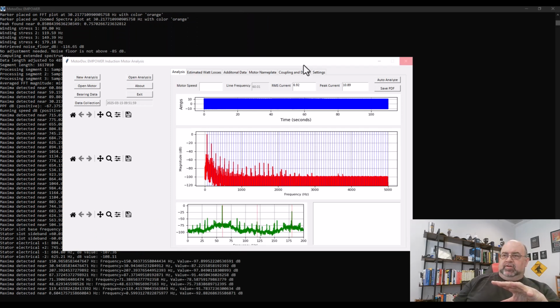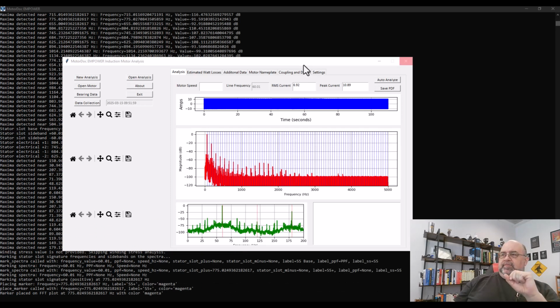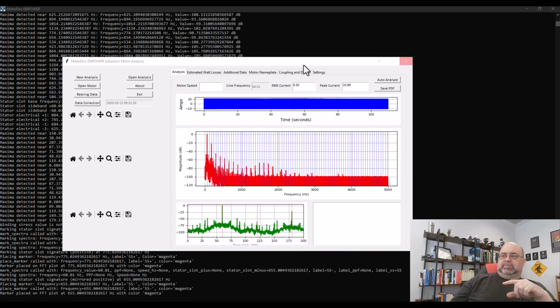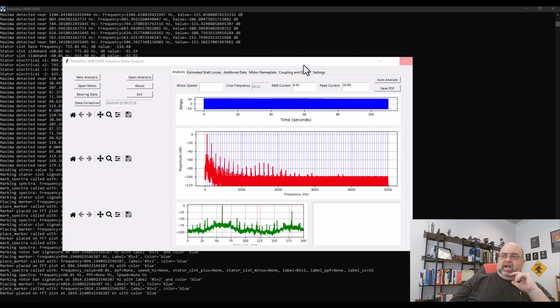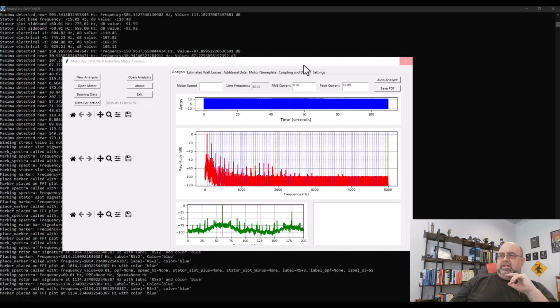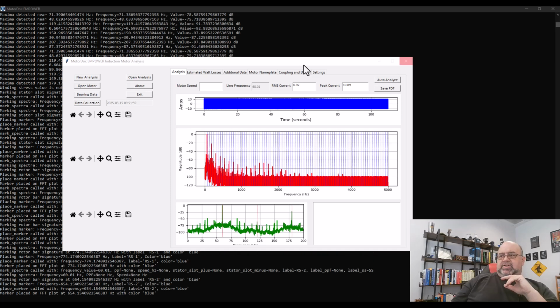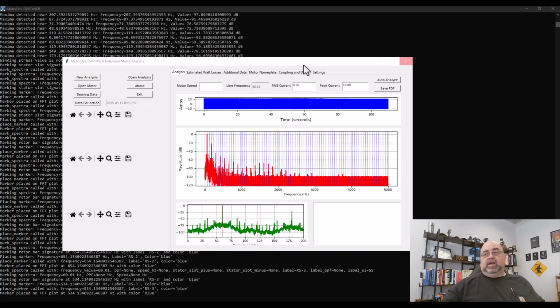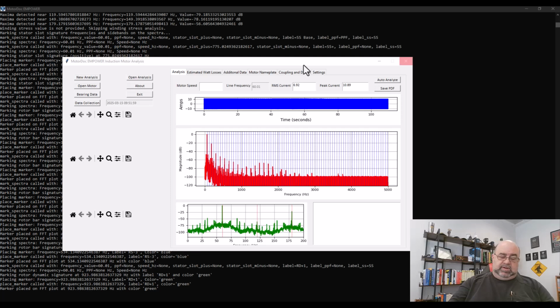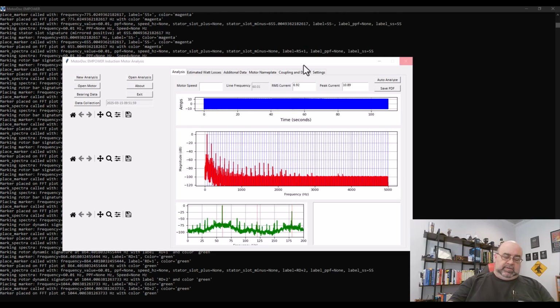Now, it wasn't heavily loaded, so 6.9 amps from the higher one. That particular crest factor, 10.89. Let's see what that is: 10.89 divided by 6.92, crest factor 1.5. So there are harmonics present, by the way.